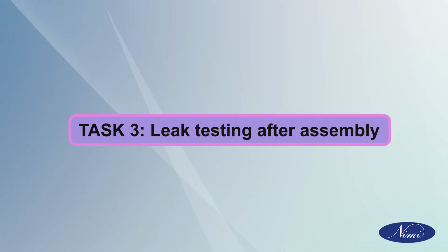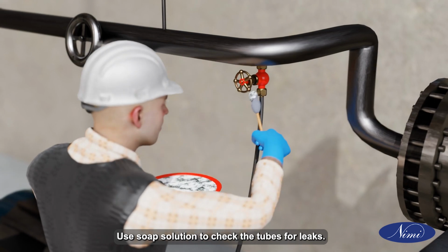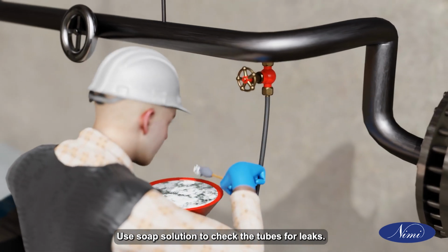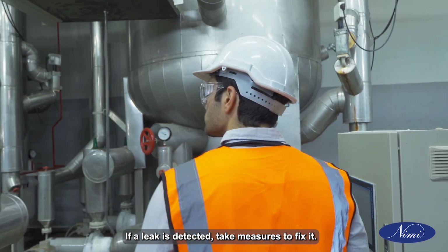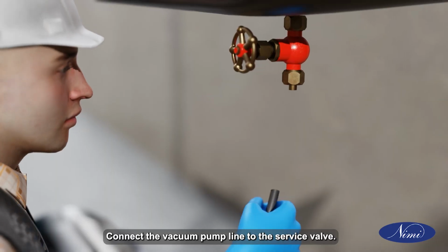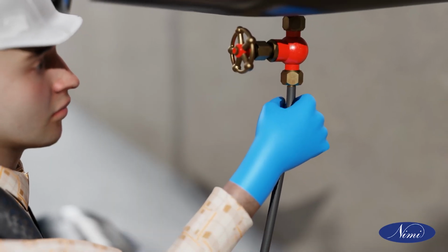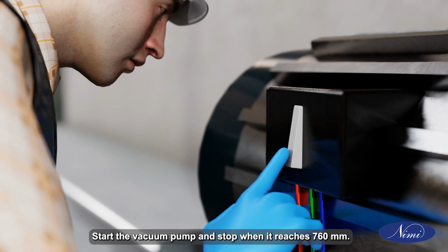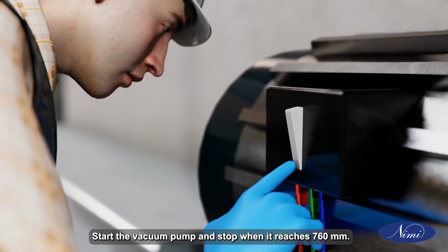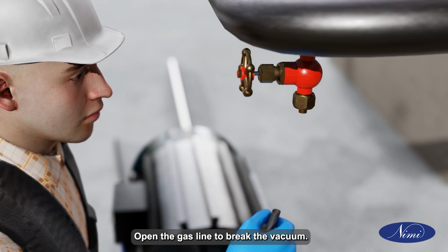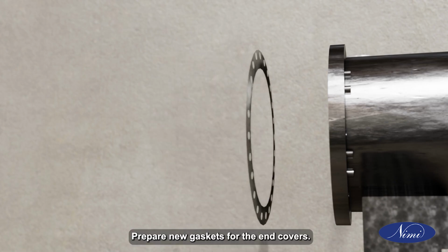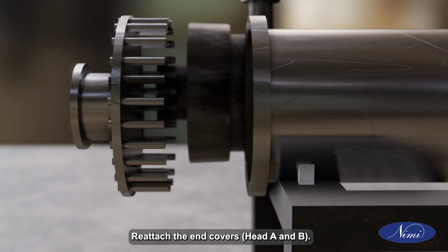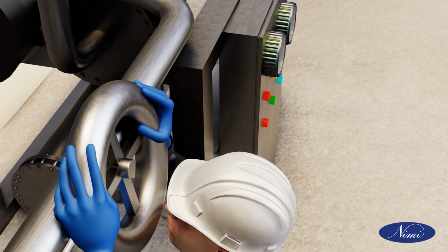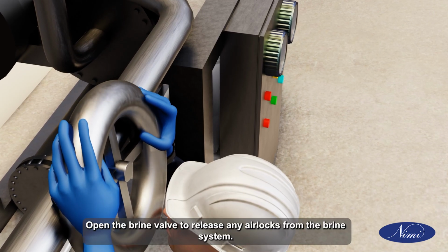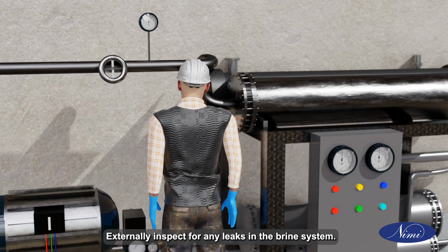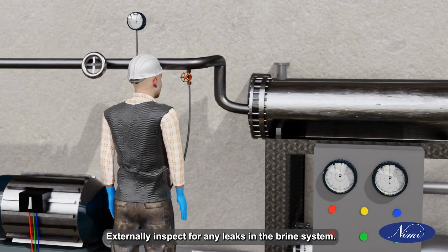Task 3. Leak testing after assembly. Use soap solution to check the tubes for leaks. If a leak is detected, take measures to fix it. Connect the vacuum pump line to the service valve. Start the vacuum pump and stop when it reaches 760 mm. Open the gas line to break the vacuum. Prepare new gaskets for the end covers. Reattach the end covers, head A and B. Open the brine valve to release any airlocks from the brine system. Externally inspect for any leaks in the brine system.